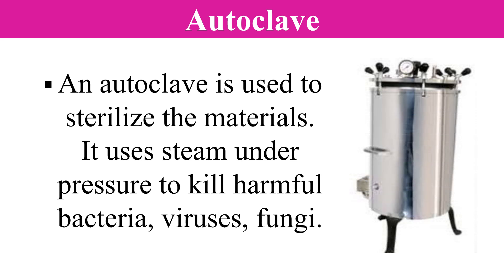The next instrument is the autoclave. Each and everything used in the plant tissue culture experiment should be properly sterilized. Sterilization can be done by many methods, and one of the most commonly used is wet sterilization, done by autoclave. An autoclave sterilizes material using steam pressure and temperature — generally at 121 degrees centigrade for 15 to 20 minutes at 15 psi.